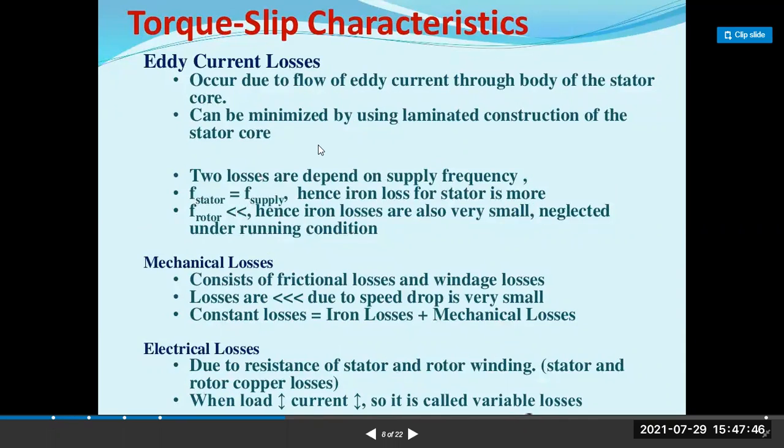Okay, so these are the magnetic losses. Now, the next point is mechanical losses. Mechanical losses are mainly friction and windage losses. Friction loss is due to the rotating part, because an induction machine is a rotating machine. So we can encounter friction, air friction, or machine friction. So there will be a friction loss. The second one is windage loss. Windage loss is due to the air resistance on the peripheral of the rotor part. The combination of friction loss and windage loss is named mechanical loss.